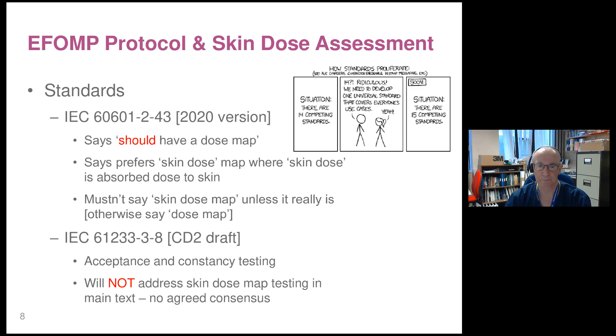There is also, in the general X-ray equipment standard, something that says the following. Accompanying documents shall, that means it has to, contain certain instructions for manufacturer recommended quality control. Now, looking at all those answers to the polls, it's absolutely clear that very few of you have been given information from the manufacturer of the X-ray equipment on how their models actually work. Some do, but even fewer of them will tell you how to test it. And I looked recently, just as an example, at a Philips Azurion instructions for use with all the accompanying documents, and I couldn't find anything in there that they were recommending me to go away and test their in-lab skin dose map. Now, this standard applies to interventional as well. So whether this is something that we can enhance in further versions of these standards, we'll wait and see.